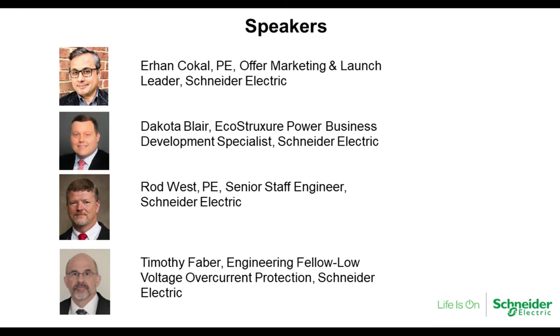So the ArcBlok system, after having the first incident, clears the arc so fast that there is no damage to the vault section that Tim explained. So you may continue to service. You can continue to energize and continue to service the equipment. And of course, you may need some cleaning and small maintenance, but in the testing process, we tested over 6 times and it was still continuing. So it's a huge innovative approach for arc flash incident energy mitigation because of this feature.